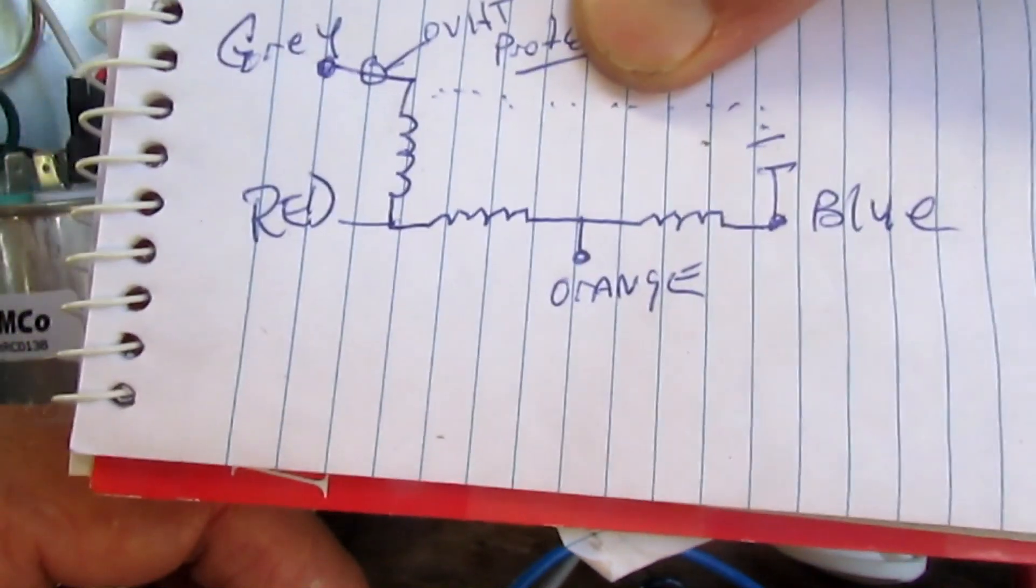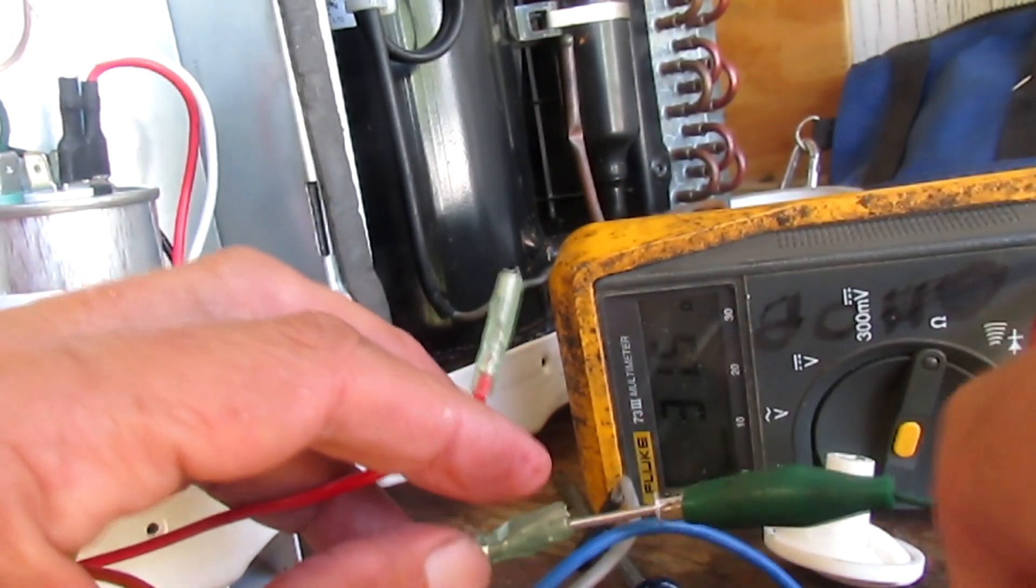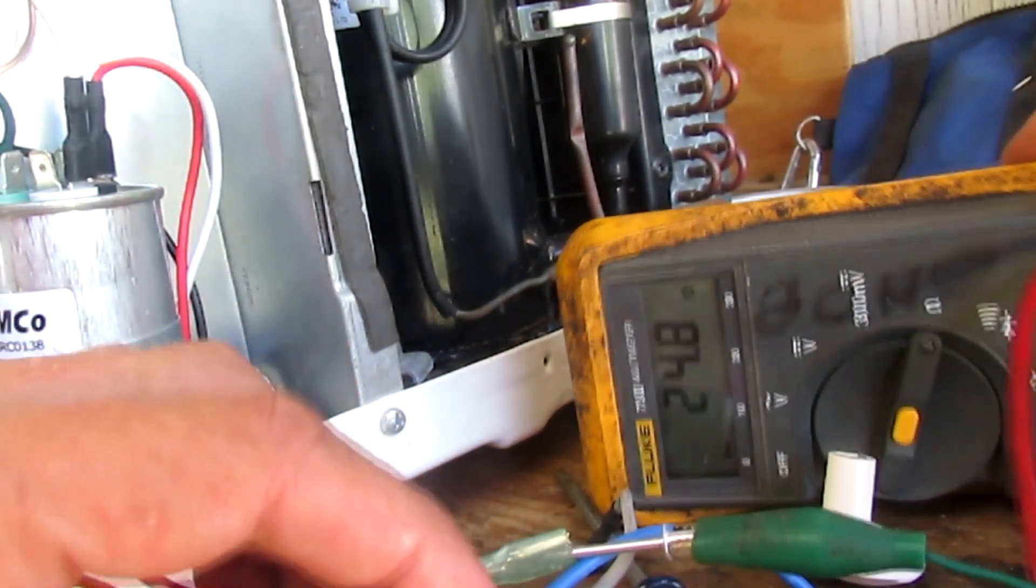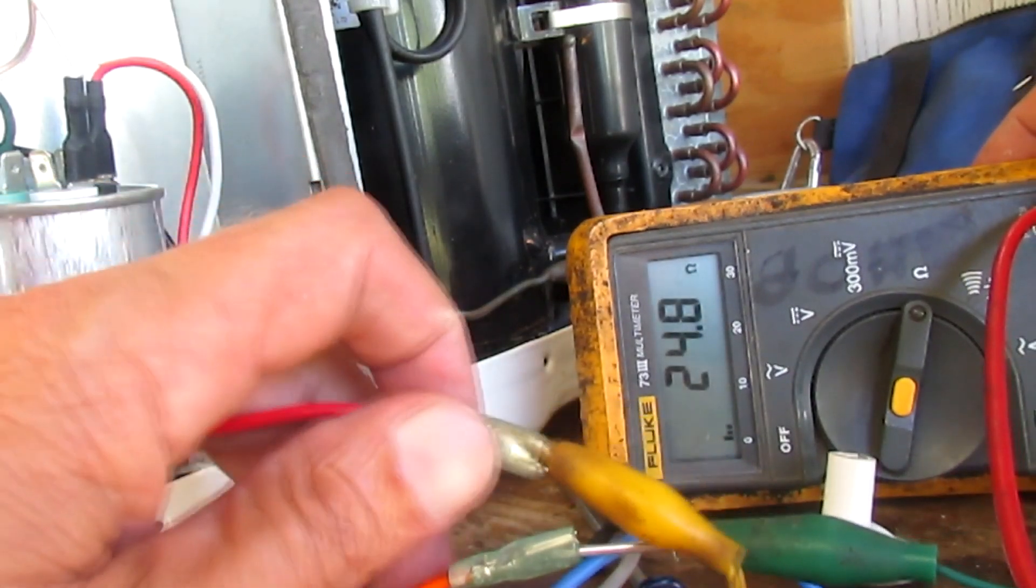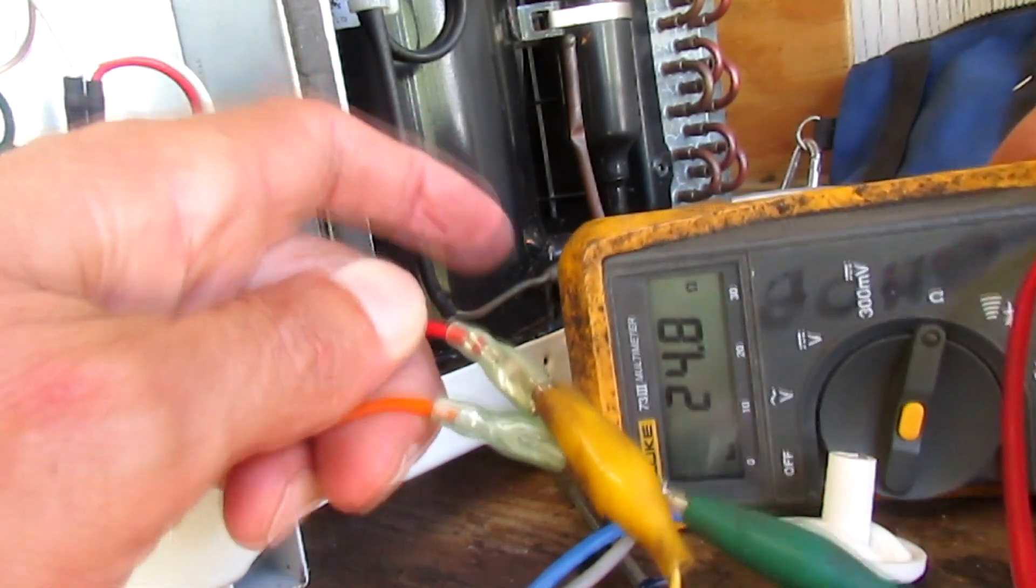And now I'm going to go from the orange to the red to make sure that wire is good. I don't know if that's the right reading for this motor, but I know it's not shorted out and I know it's not open. So I'll leave my meter lead in the orange and I'll clip this one onto the red. And what do I read? 24.8. I know it's not open and I know it's not shorted, so I'm going to assume that's probably good.